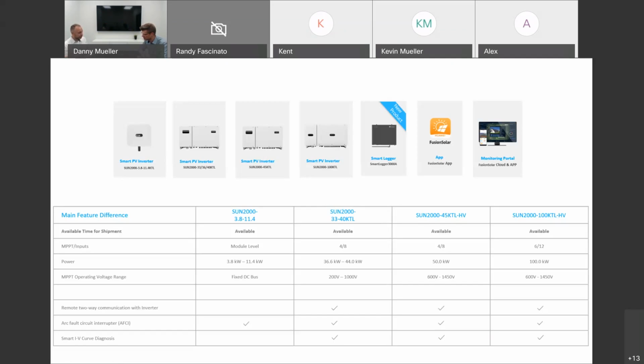Then we have a 480 volt unit. That's the Sun 2000 33 to 40 KTL. So that's 36.6 kilowatts to 44 kilowatts. Similar reason as the 45 KTL, the Canadian market has a power factor of 1. The MPPT voltage range is 200 volt to 1000 volt. It has all the same features as the 45 KTL, so the remote two-way communication, the arc fault, and the smart IV curve diagnosis.